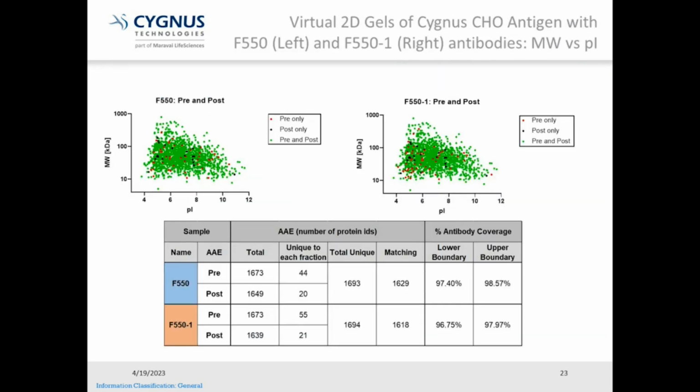Ideally, once the selected host cell protein analysis method is qualified and validated as fit for its intended use of process monitoring and product lot release, it is imperative to ensure that critical reagents supporting the validated host cell protein analysis can last throughout the lifetime of the program, from supporting phase 1 to phase 3 clinical trials and post-market product life cycles.